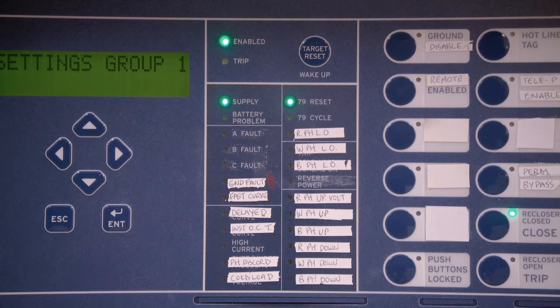High current. This will indicate upon tripping on a high current. This feature is typically not programmed in the distribution system. Cold load pickup. This unit has a second set of settings, which can enable a cold load pickup. After lockout has occurred and reclosing is taking place, enabling this function will allow more load to be carried without causing another fault until the system current balances out.